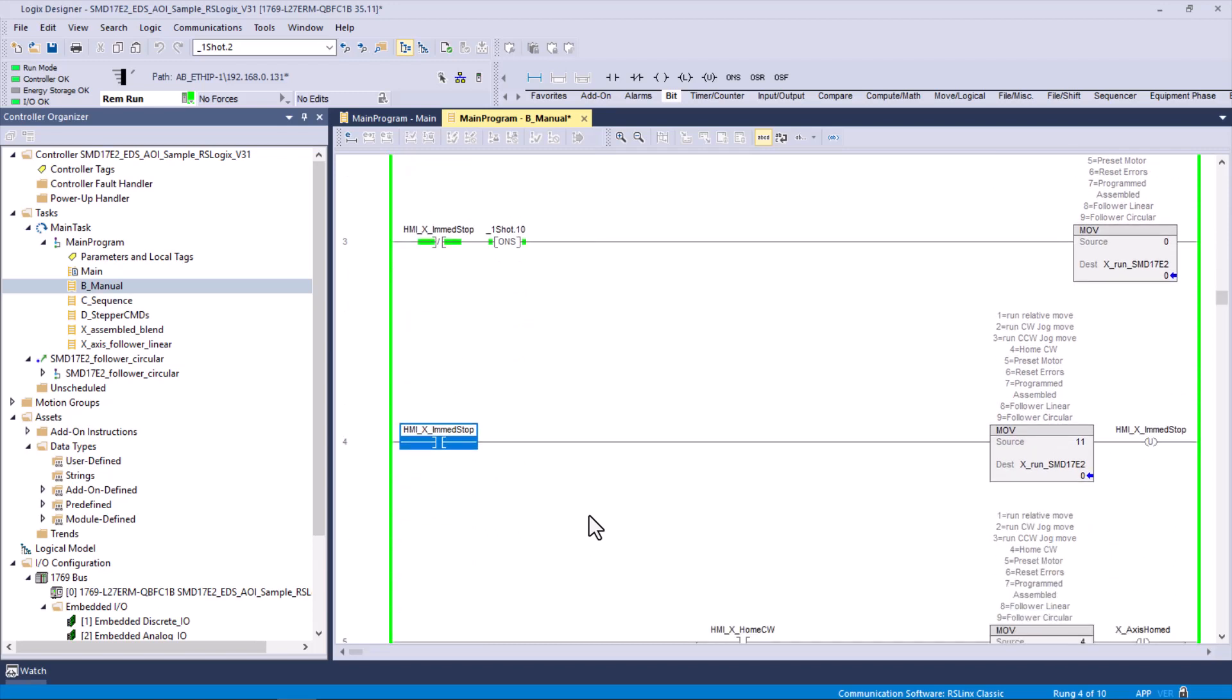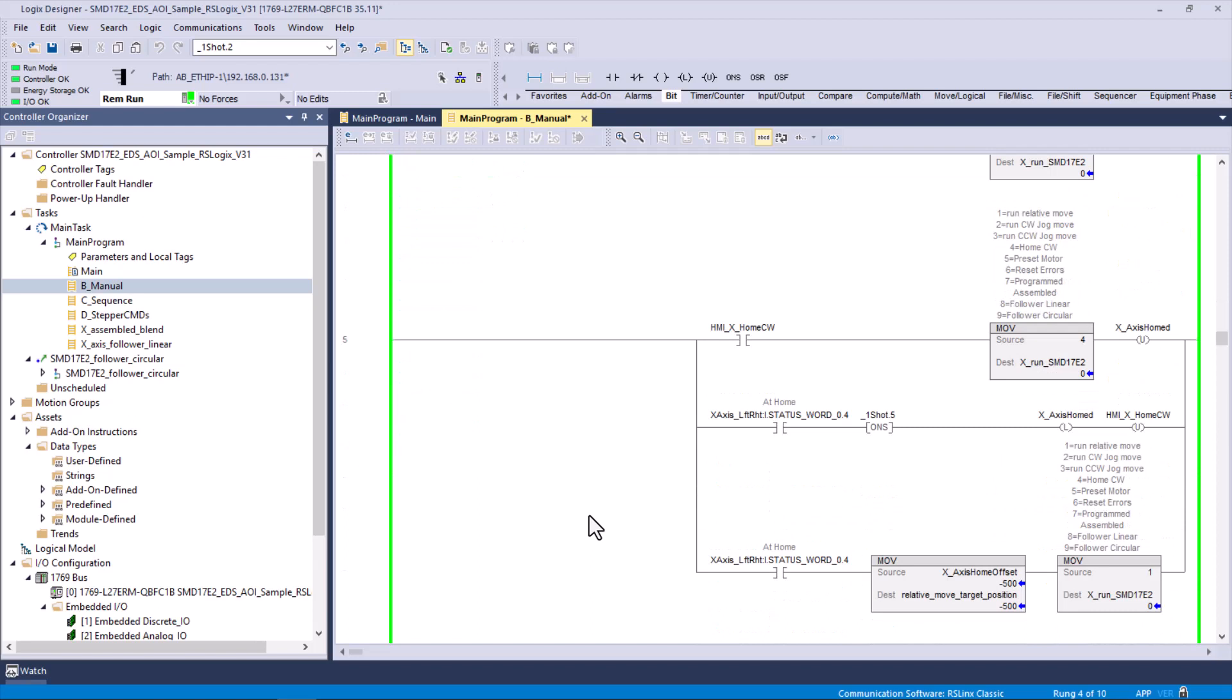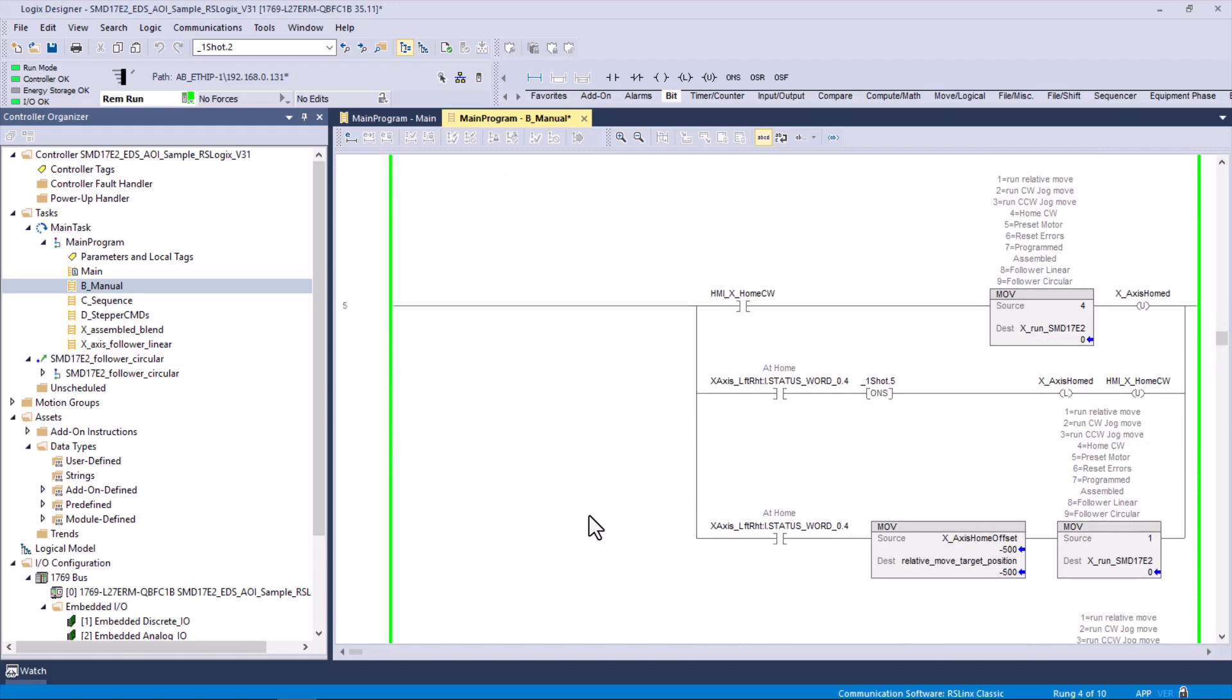I put in these two rungs to clear errors and to do an immediate stop. Sometimes you're doing something and you don't want to hit an e-stop, but you want to stop. These motion instructions, typically once you start them, once the dogs are loose, they're loose. There's no turning off the request. You have to do an immediate stop or hit the e-stop. I also needed a home function. You remember that in the dashboard I had set the configuration for one of the inputs to be a home switch, and on our little fixture I have two proxies and a micro switch to cover the home positions for all three axes.